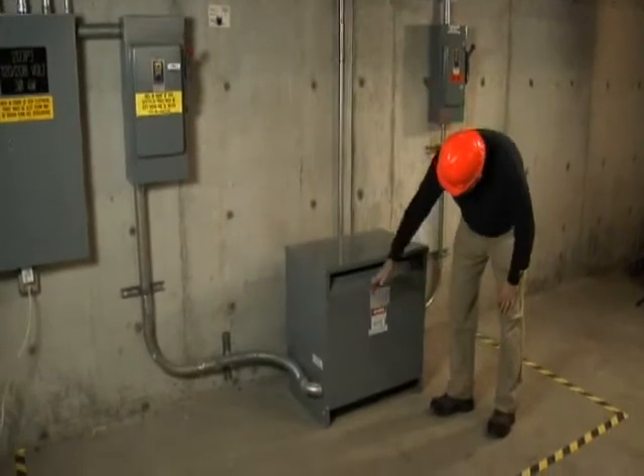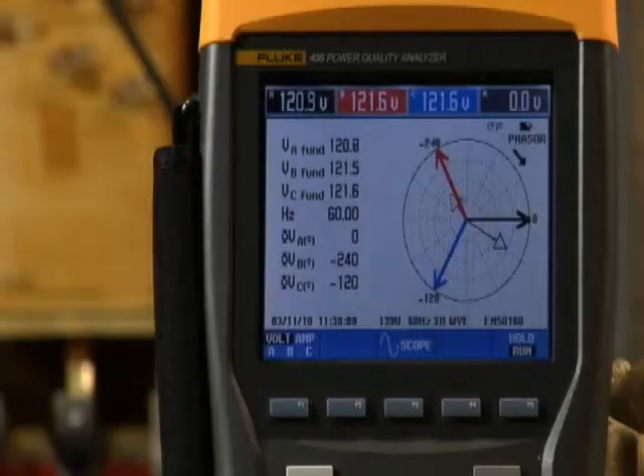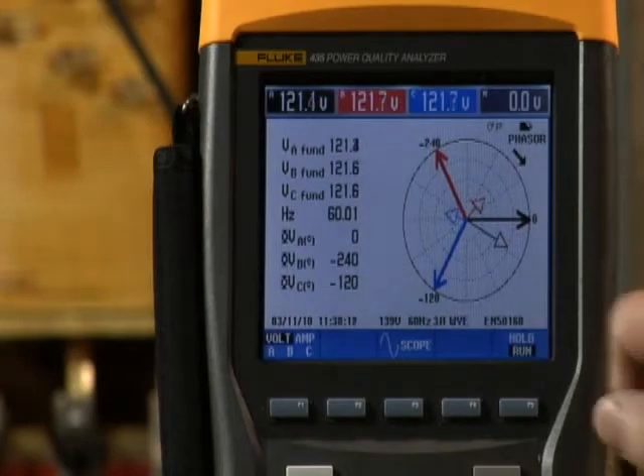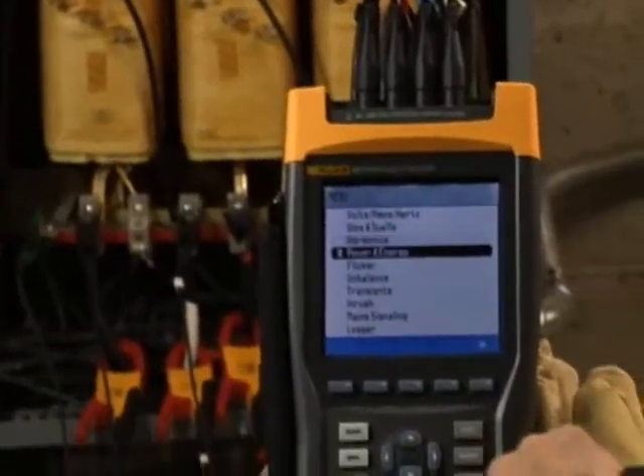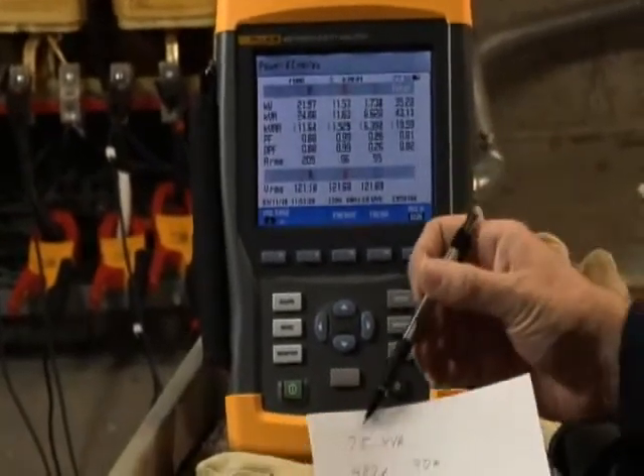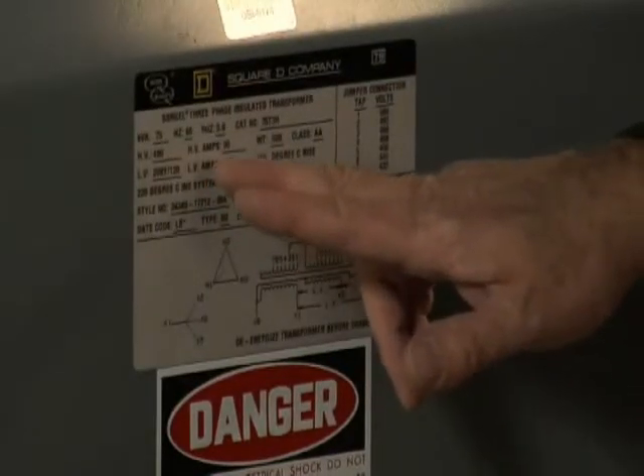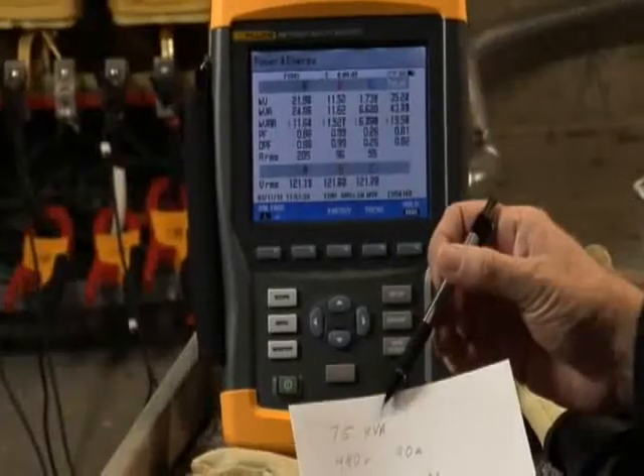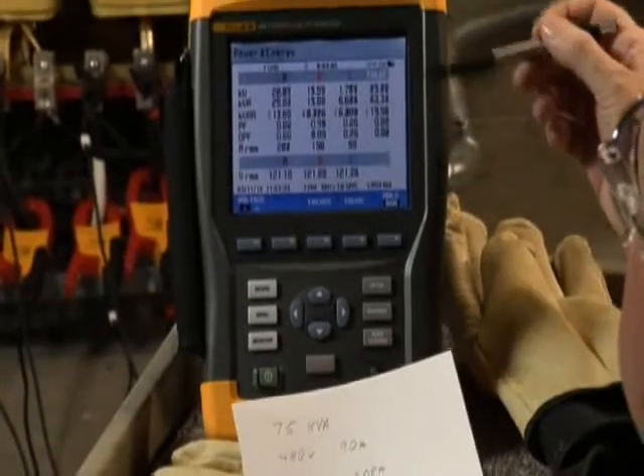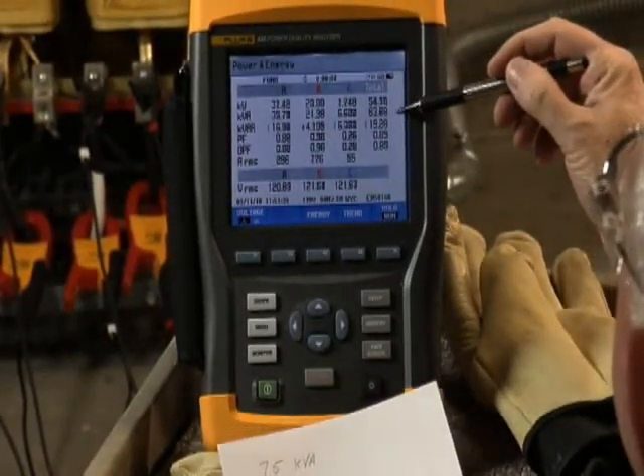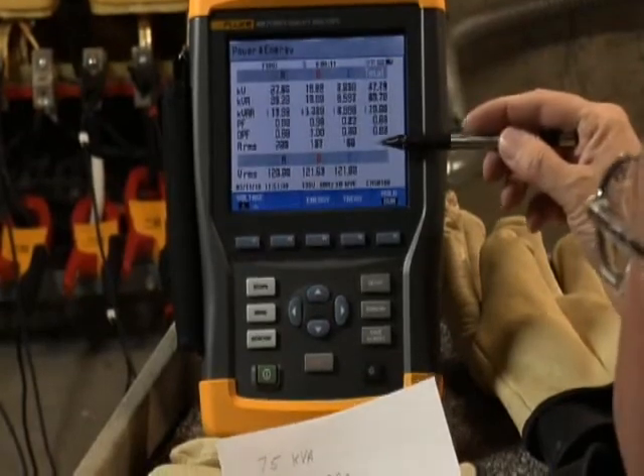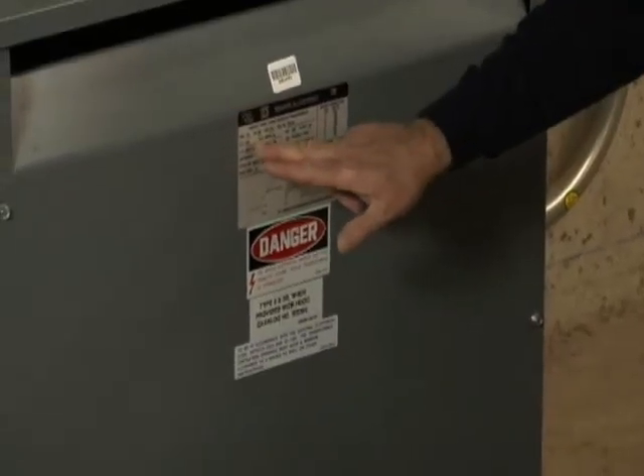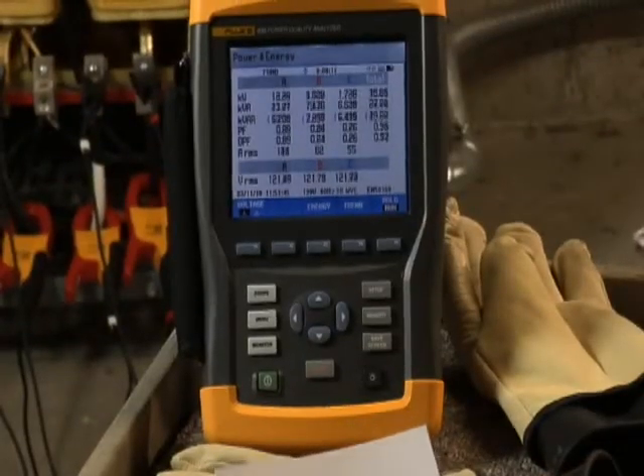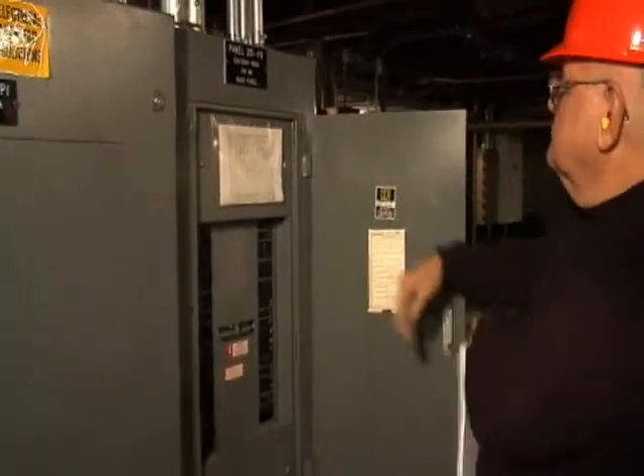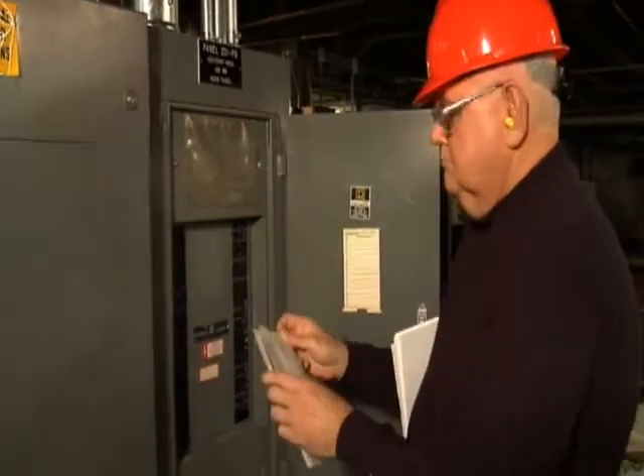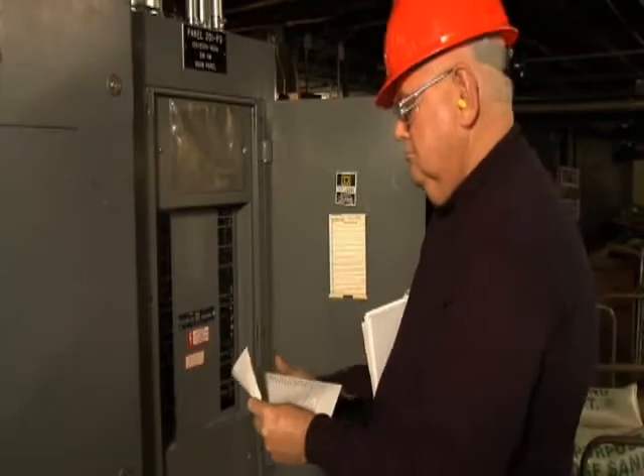Let's talk about a transformer that's running hot. Start by checking for overload. Check the power readings on the Fluke 435 power quality analyzer. Compare kVA, voltage, and current against the notes you took from the nameplate earlier. If the actual power consumption you see is less than the nameplate, check for unbalance or harmonics. If you don't find an unbalance or harmonics issue, the transformer's cooling system may not be functioning properly. If the power consumption you see is greater than the nameplate, you have an overload issue. Evaluate the consumption at the loads downstream and evaluate the overall load schedule and capacity. You may need an additional transformer.